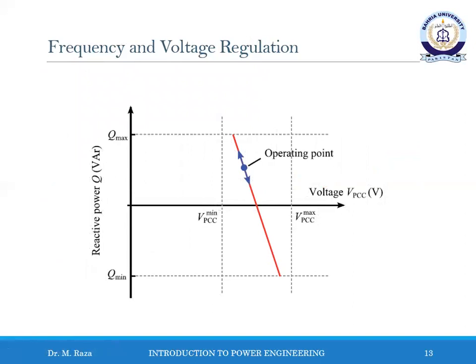Another grid stability index is the voltage level. By controlling the reactive power, the voltage level is regulated, which is known as automatic voltage regulation. The reactive power exchange between the distributed generator and the distribution grid can change the voltage profile at the point of common coupling. Here, the abbreviation PCC means point of common coupling. The grid code for voltage regulation is illustrated in this diagram.